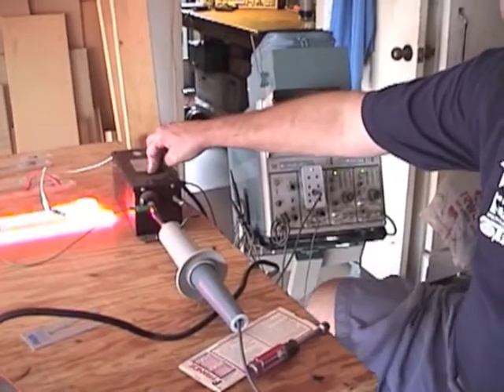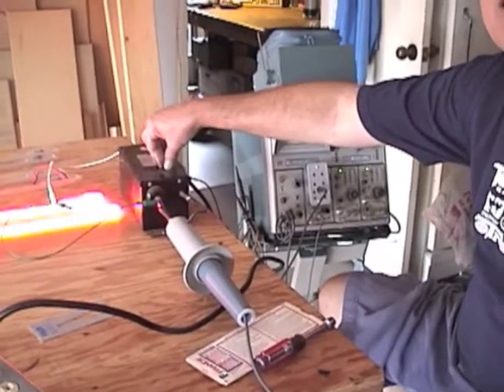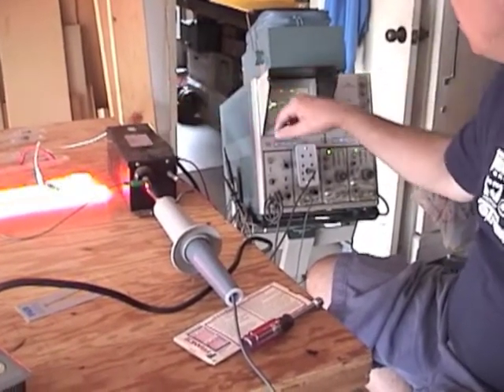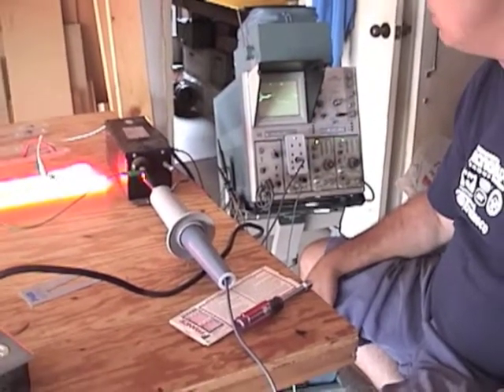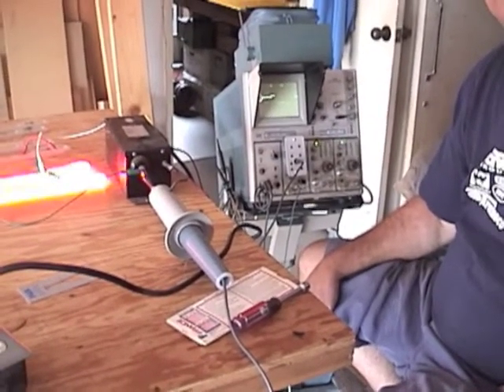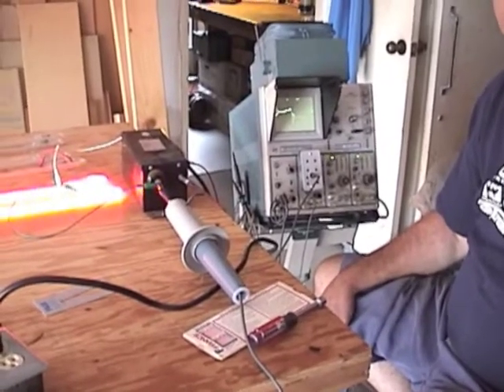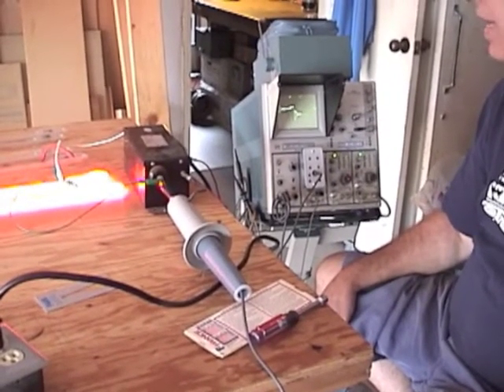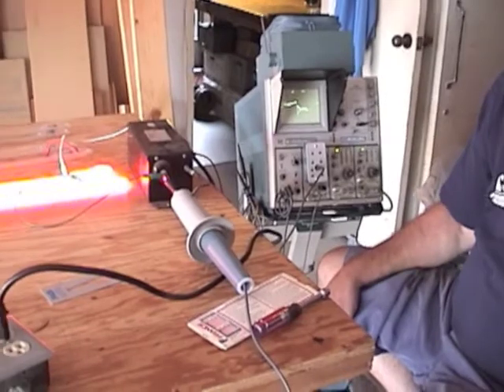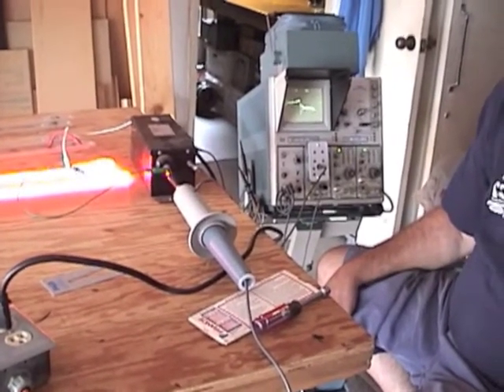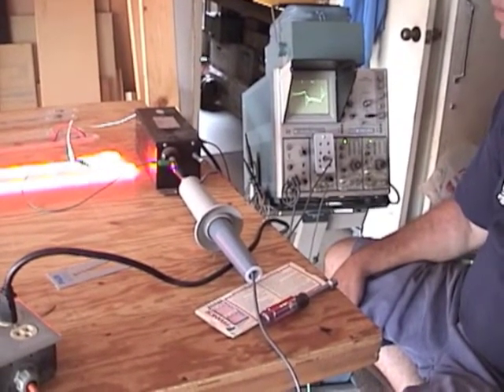But if we're wiring with GTO, 15 kV GTO, even with the spikes we're hitting 4 kV rather than 8. So while the tranny may not be happier because it's all a red tube load, the GTO will be happier - it's under less voltage.